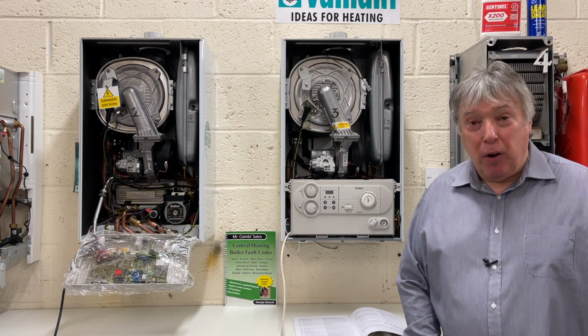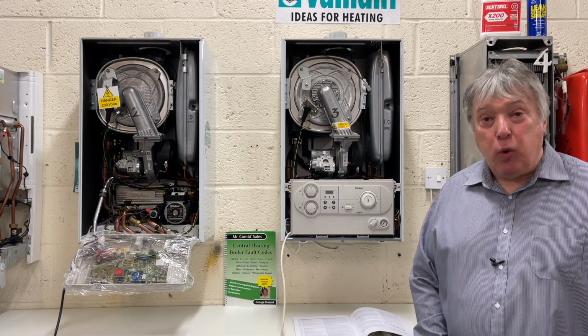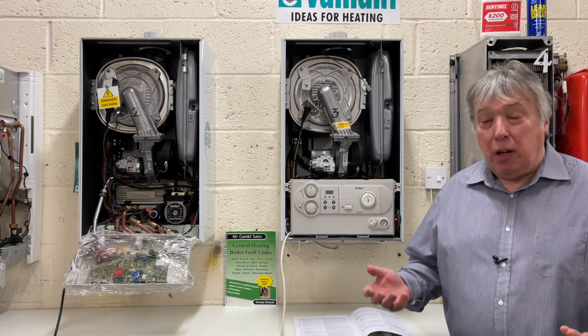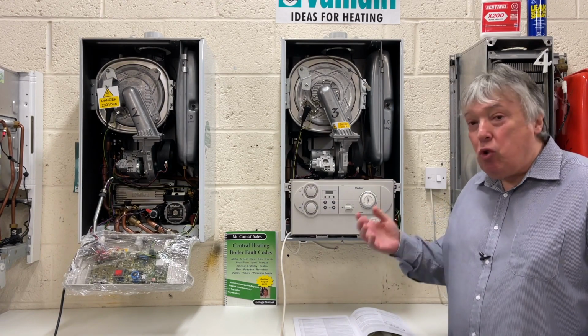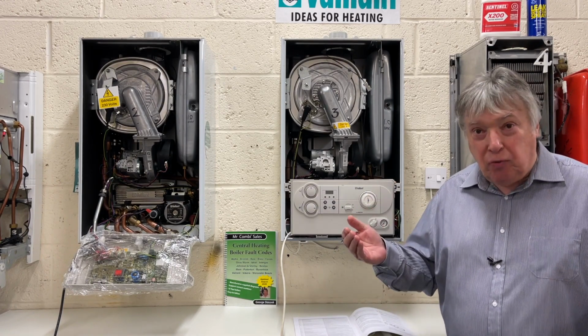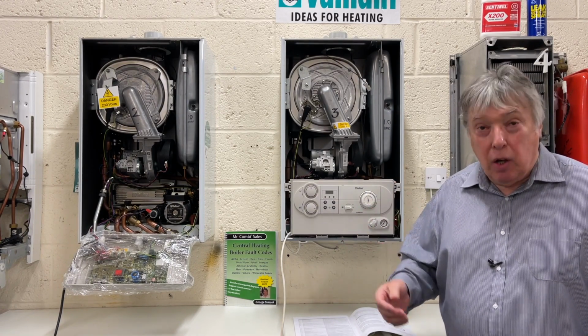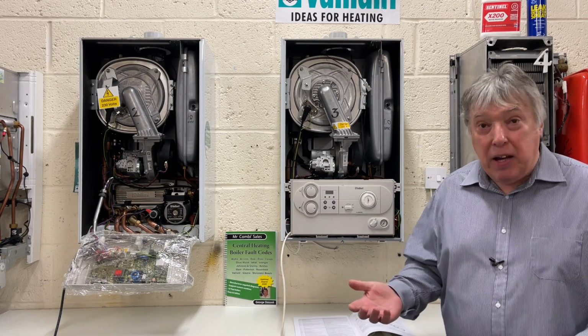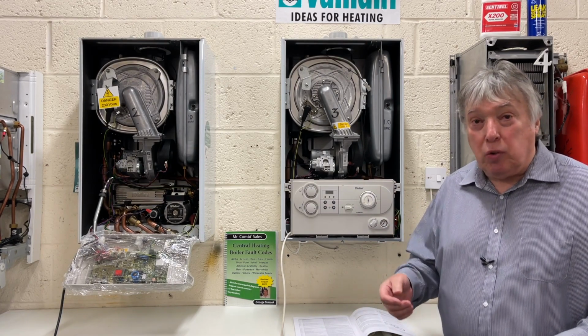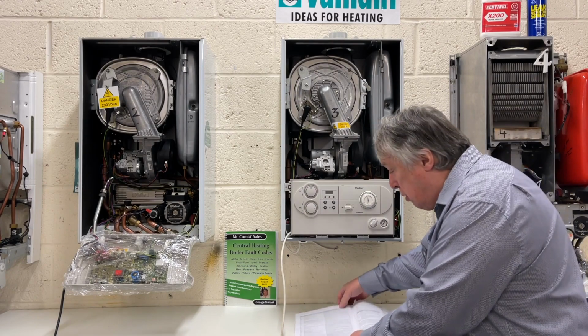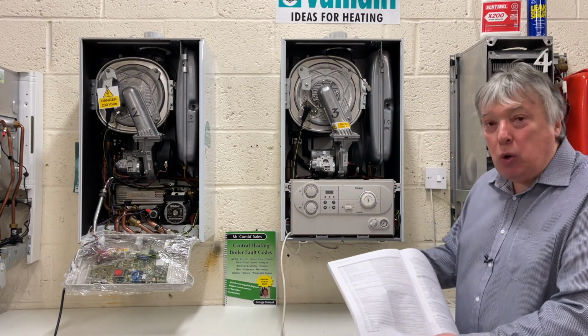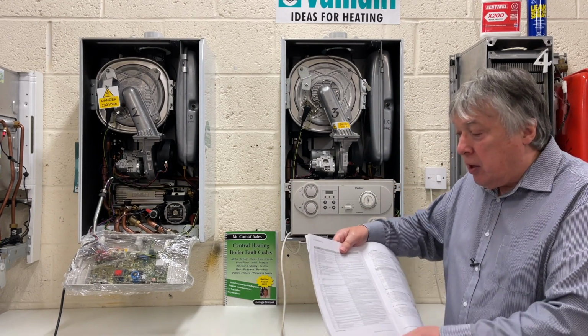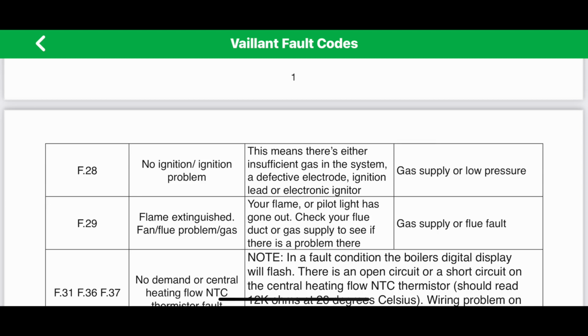Another popular fault code is F28. And basically what that means is that there's something wrong to stop it not just firing up, but actually working. So it could be lack of gas or electricity or something else. And if you look in the manual, so this is an Ecotec 28, and if you look at F28, you can see there's a whole paragraph here. I'll do some close-ups so you can see exactly. There's a whole load of them.